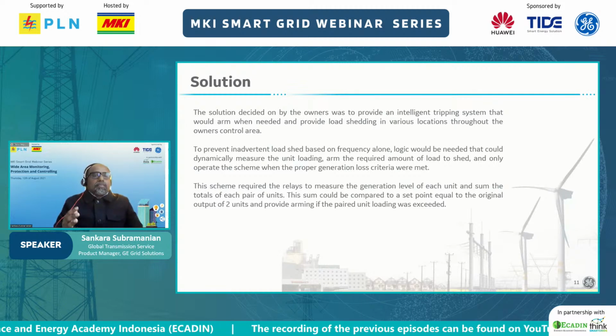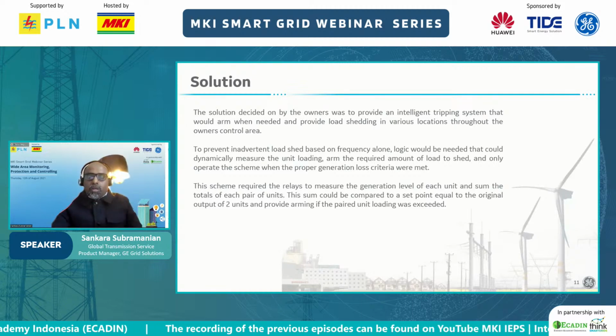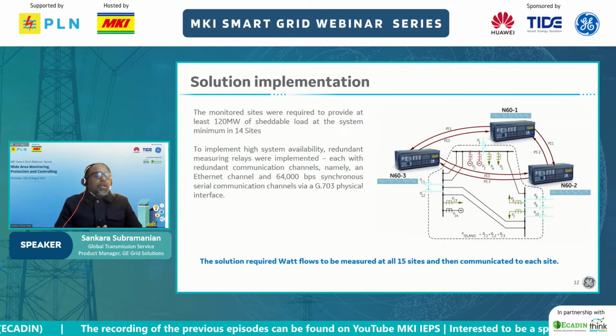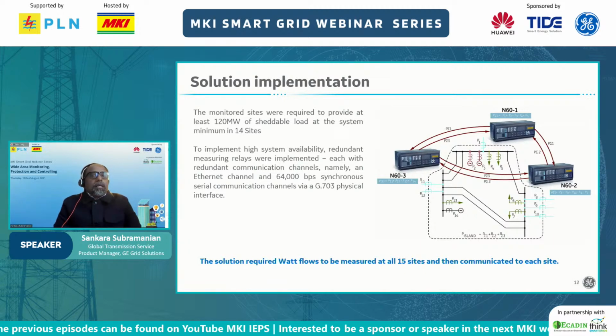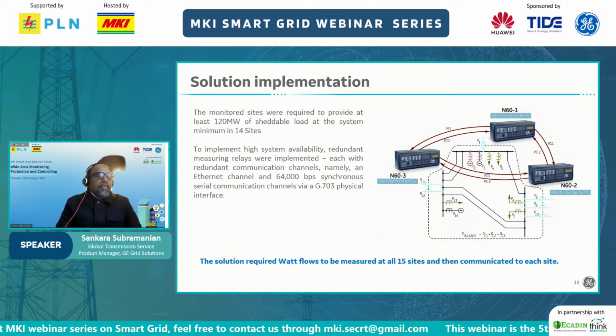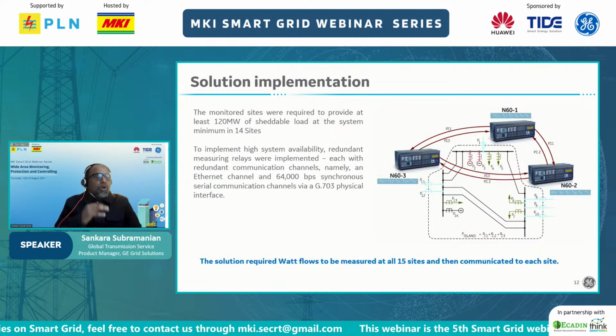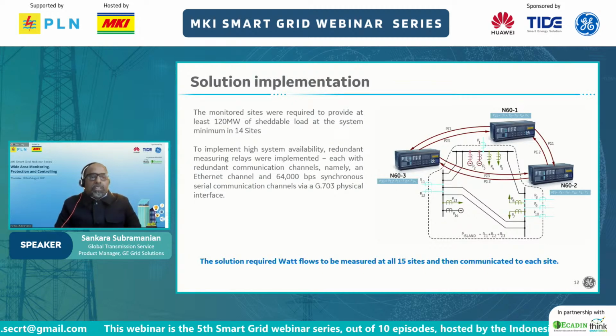The solution was worked out to provide high availability through a redundant scheme, with redundant relays and redundant communication channels. As you'll see in the next slide, one channel was over Ethernet, and the other was over 64 kbps serial comms via G703.